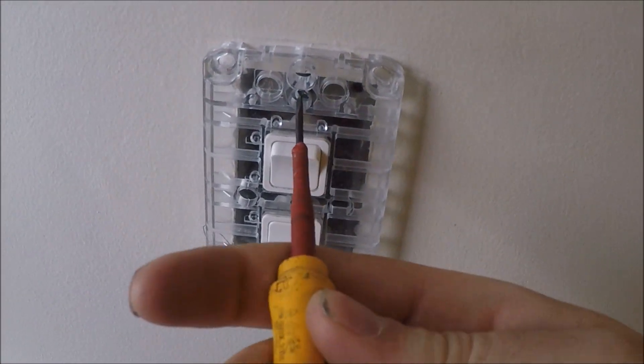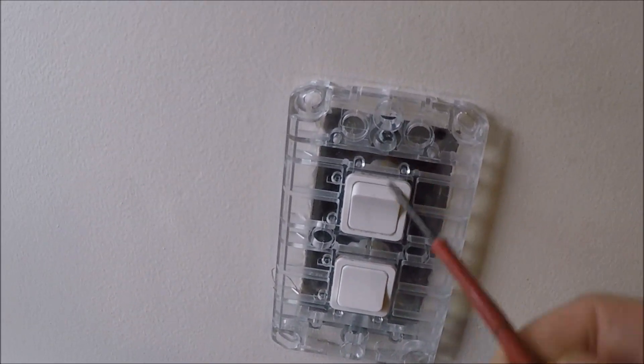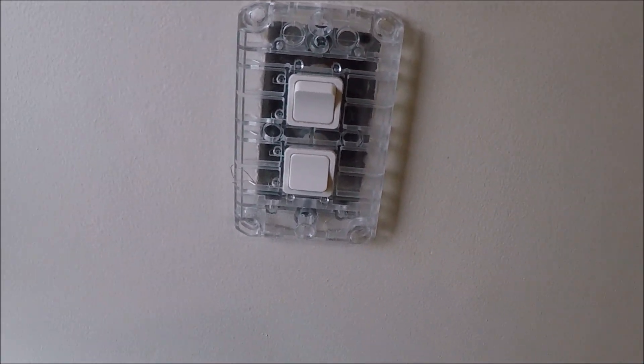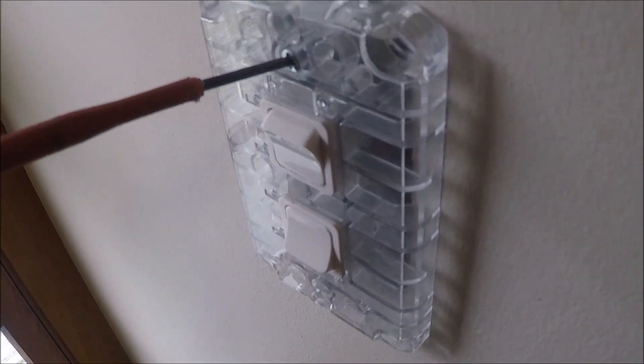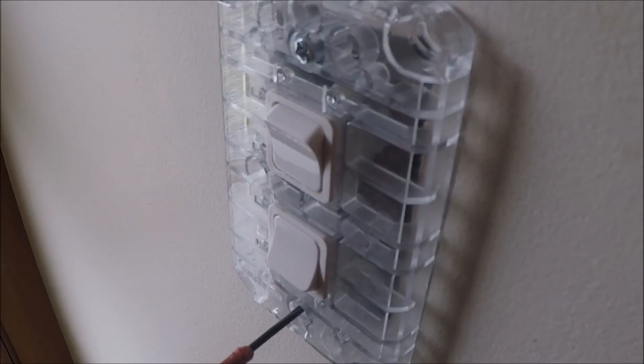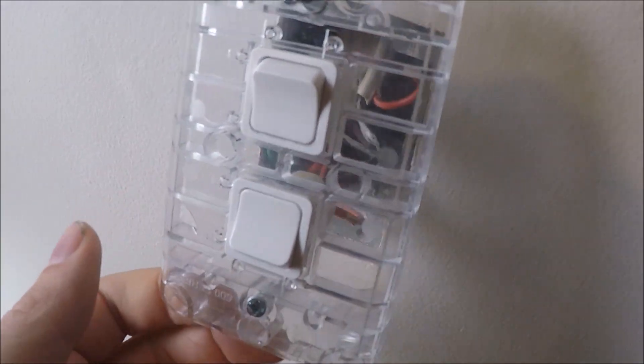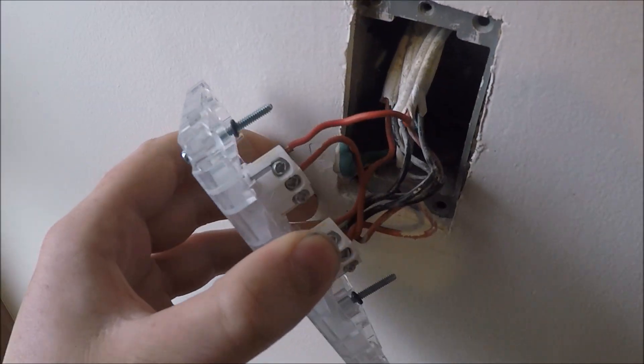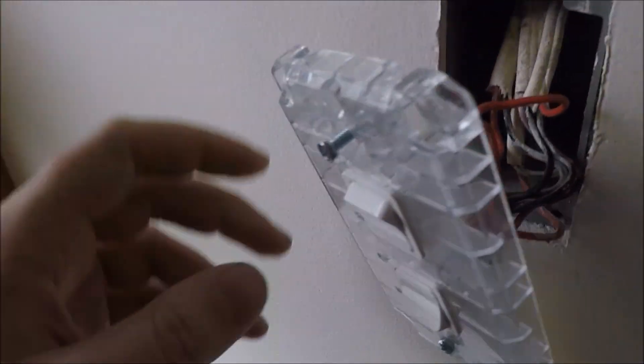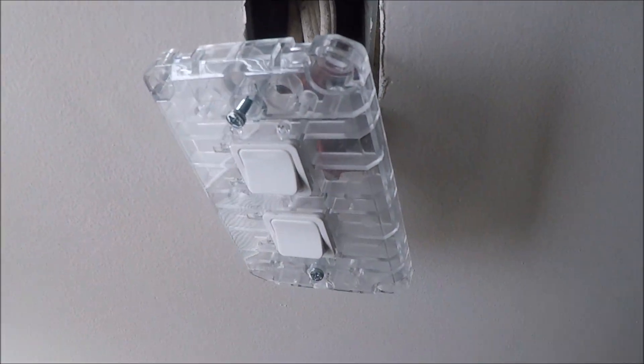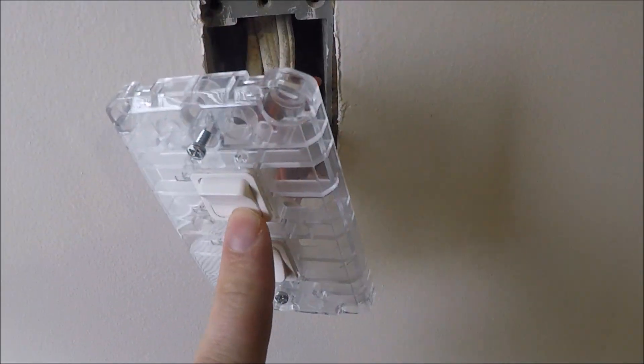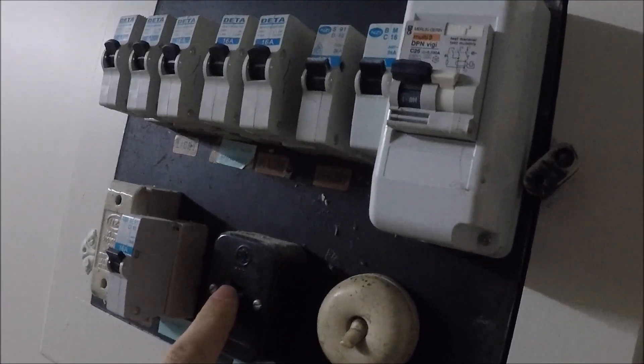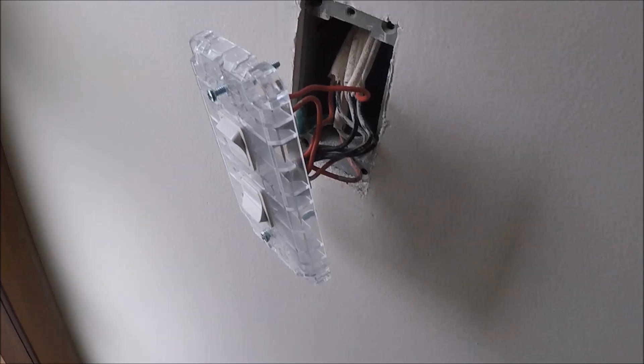Next thing you want to do is unscrew the two screws from the flush box. Once it's done, if you haven't already, kill the power. Do not touch any of these cables on the back. The best way to do that is to turn your lights on, go to the switchboard and switch either the main switch off or lighting circuits, these six amp ones, until the lights turn off. Once you switch the breaker off...